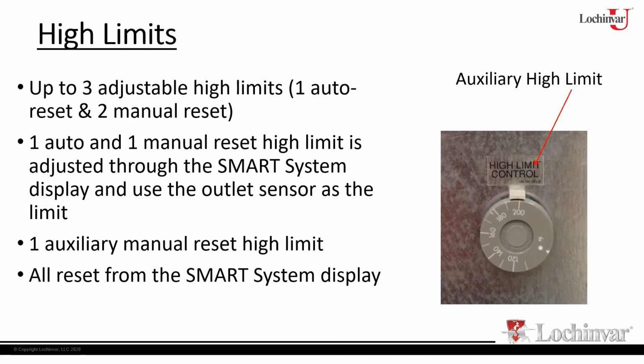This one is there to meet code requirements. Now it's a manual reset, but it's going to be reset through the display. So you don't have the red push button here on it. It's going to be reset through the display. So 2 manuals, 1 auto. Now the limits that are built into the control module, we're using the outlet sensor.